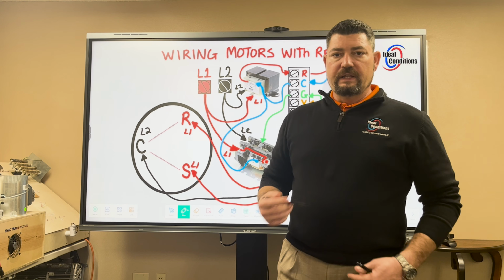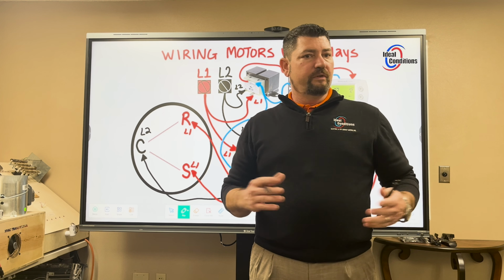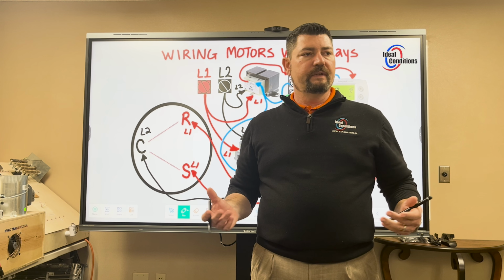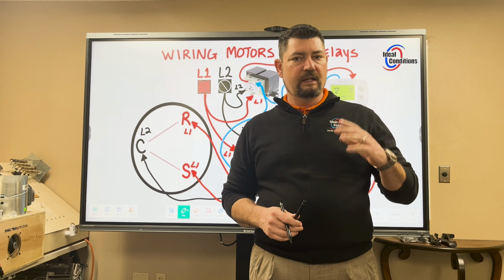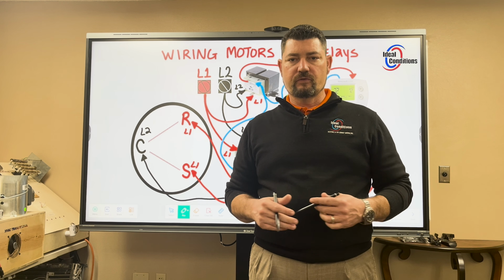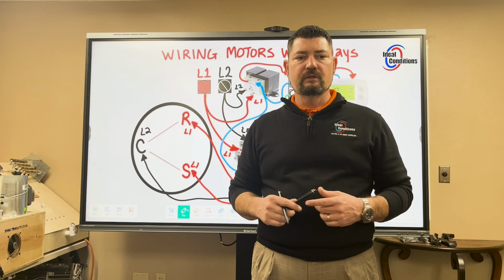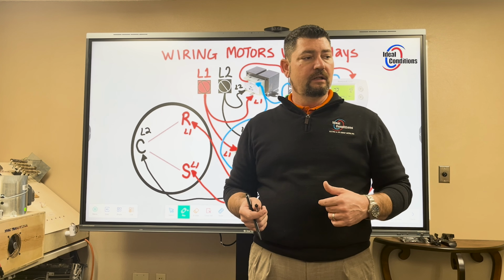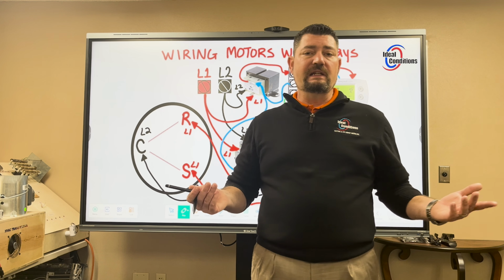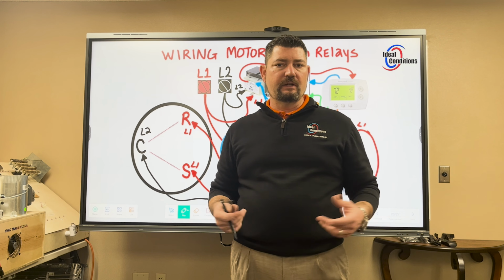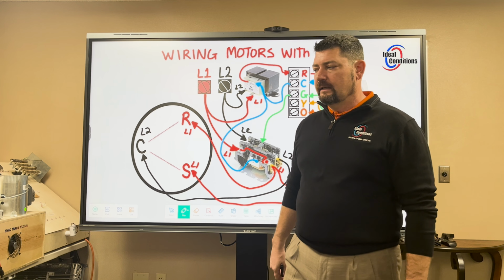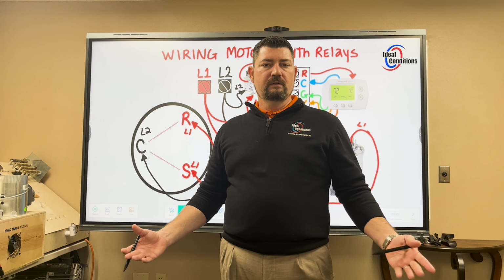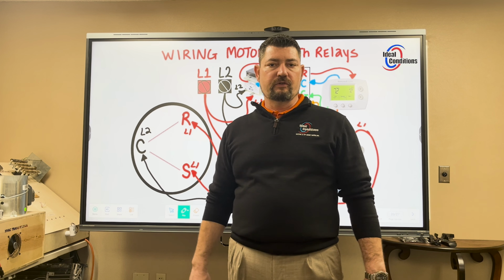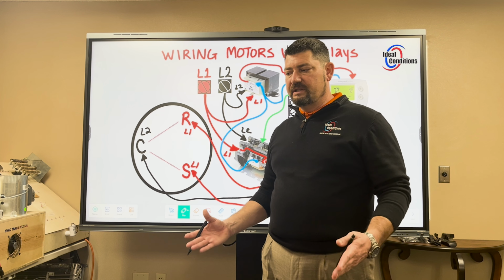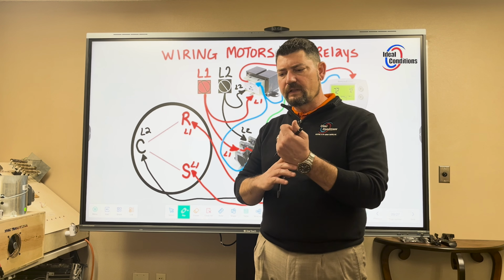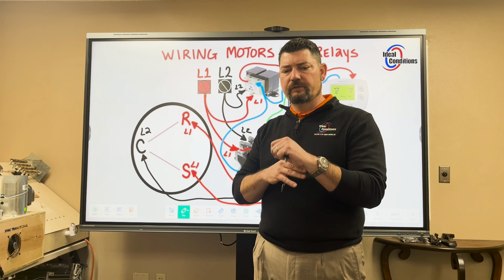We're going to continue to release videos, just picking a different relay each time. Once we're done talking about the majority of the relays out there that you'll find helpful, we're going to get into the fan control boards, fan managers, and stuff like that, and then into ECMs being controlled with those boards or relays. There's not a whole lot to talk about with ECMs by themselves, but all this is on standard air handlers, which are a very large portion of our market in the U.S. That's why I chose that particular model. It doesn't matter the manufacturer, the intentions are all the same: the motor's got to come on anytime there's a compressor running, right?